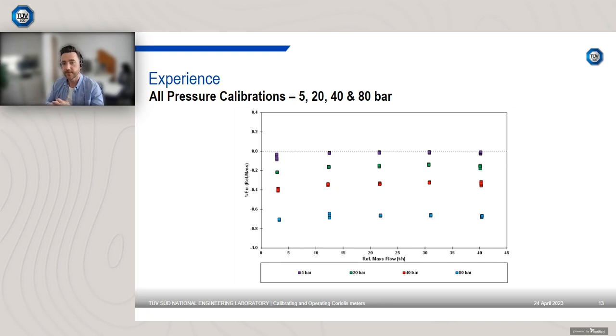Now if we include the 20, 40 and 80-bar data alongside the 5-bar, you can see that there's a significant underread, and you can see that underread starting to grow with increasing pressure. So the green data points are the 20-bar, the red data points are the 40-bar, and the blue data points are the 80-bar. And you can see that at 80-bar we're significantly underreading. Coriolis meters tend to be known as being a 0.1% device, so that's our specification, to achieve around about 0.1. Some elite models can achieve 0.05%, but mostly you're aiming for about 0.1%.